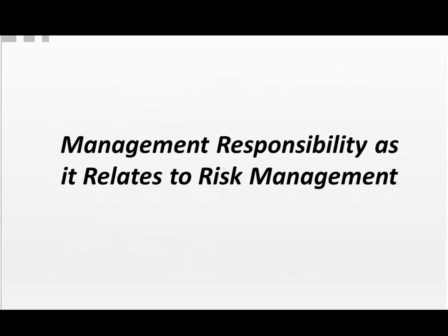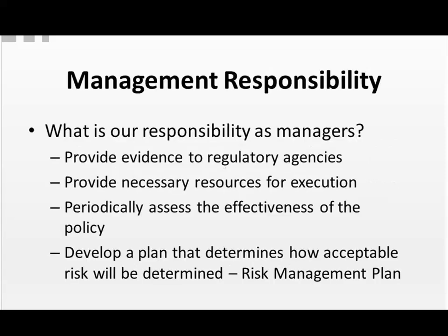Now, one of the things we need to talk about is really our responsibilities as managers, as they relate to risk analysis. Our responsibilities extend to providing evidence to regulatory agencies that the risk analysis requirement is being complied with, providing the necessary resources for execution, testing, and evaluation, and that implies that you have a plan, and instituting a policy for identifying, determining, and evaluating risk, periodically assessing the effectiveness of the policy, and developing a plan that determines how acceptable risk will be determined through this risk management plan.